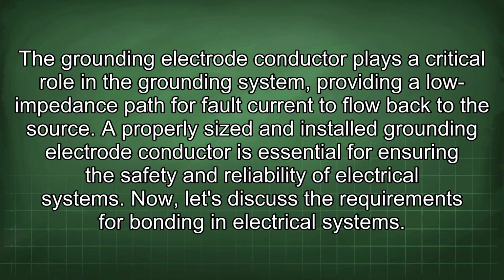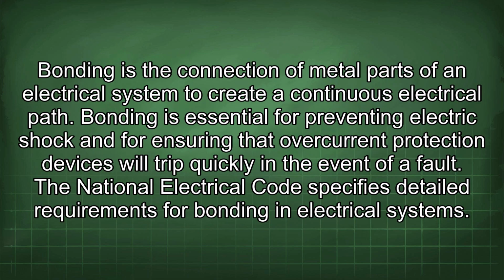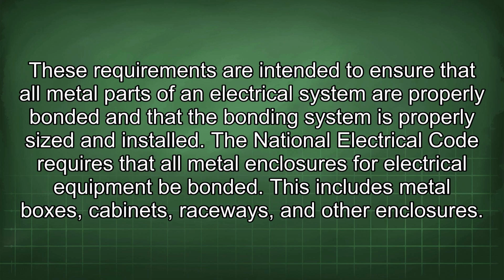Now let's discuss the requirements for bonding in electrical systems. Bonding is the connection of metal parts of an electrical system to create a continuous electrical path. Bonding is essential for preventing electric shock and for ensuring that overcurrent protection devices will trip quickly in the event of a fault. The National Electrical Code specifies detailed requirements for bonding in electrical systems. These requirements are intended to ensure that all metal parts of an electrical system are properly bonded and that the bonding system is properly sized and installed.